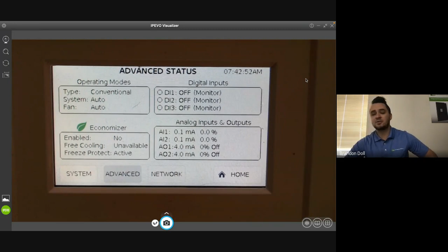As I mentioned before, the analog outs are easily able to be set up for an economizer. I'll show you how to do it, but you're going to be able to see your economizer status right from this advanced page. So right now the economizer is not enabled, so obviously you have no free cooling available, but the freeze protect is active.